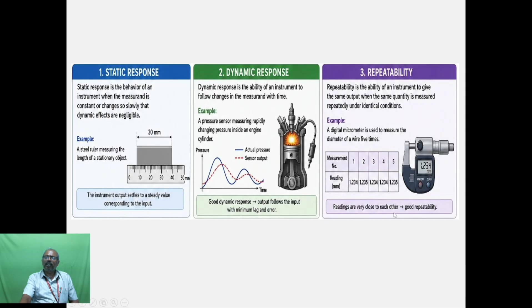Then repeatability. Repeatability is the ability of an instrument to give the same output when the same quantity is measured repeatedly under identical conditions. So example, a digital micrometer used to measure the diameter of a wire 5 times. The first time it shows the reading 1.234, second time 1.235, third one 1.234, fourth one also 1.234, fifth one is 1.235. So the readings are very close to each other. It is good repeatability.